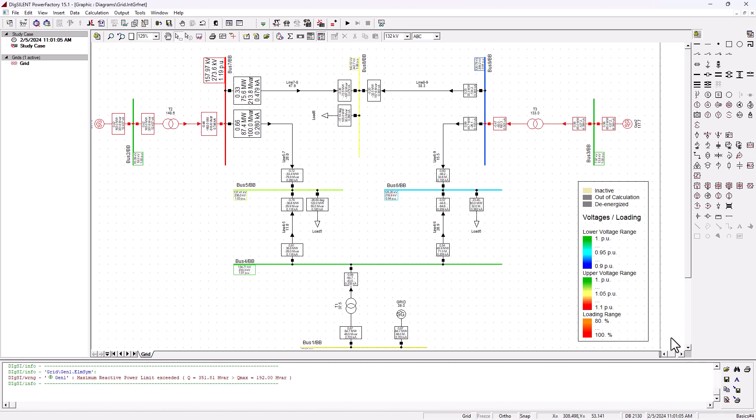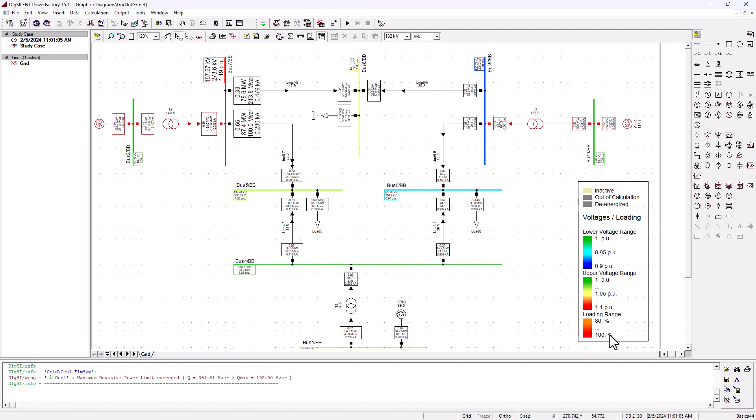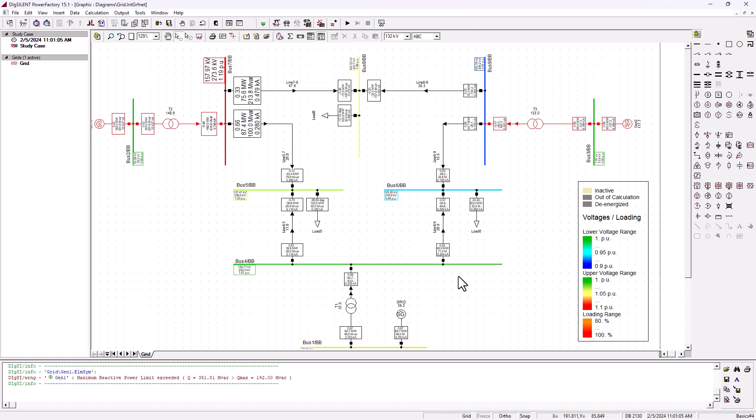We've got problems. We have to resolve these problems, otherwise the network will become unstable in the long run. We also have some of the loading ranges here. As always, red is not good. We got a range of 80 percent to 100 percent loading.